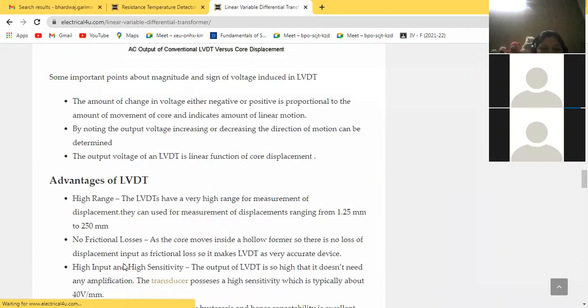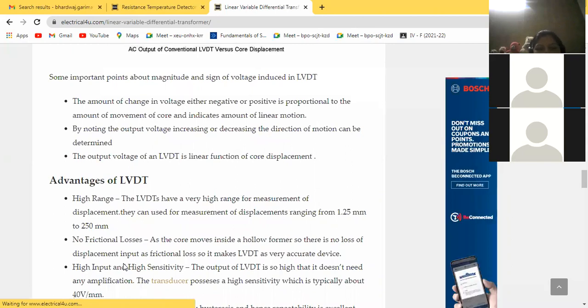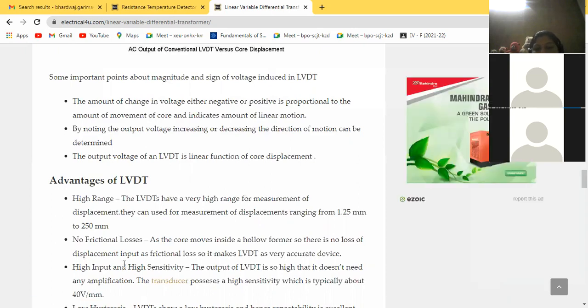Now the advantages of LVDT: high range. The LVDT has a very high range for measurement of displacement. They can be used for measurement of displacement ranging from 1.25 mm to 250 mm. No frictional losses as the core moves inside a hollow former. So there is no loss of displacement input as frictional loss. So it makes LVDT a very accurate device.